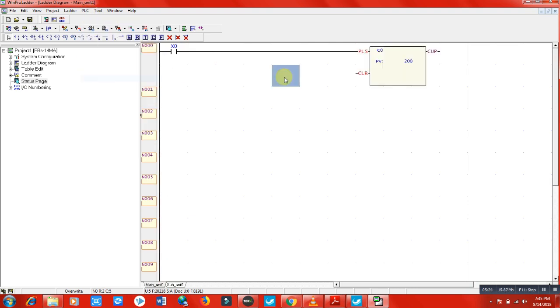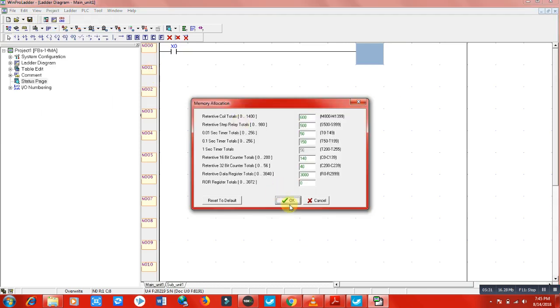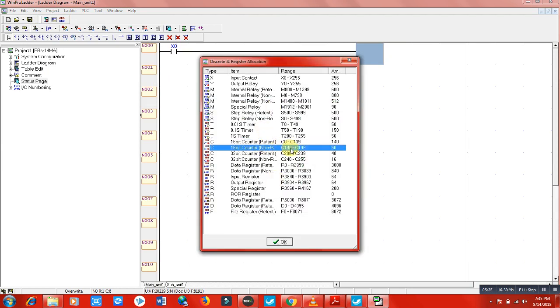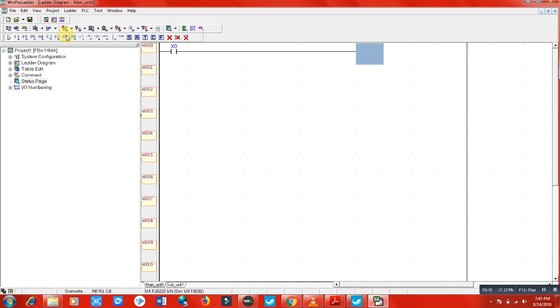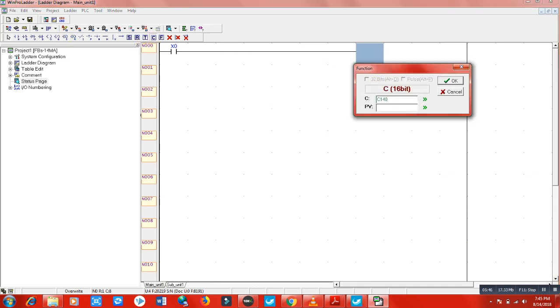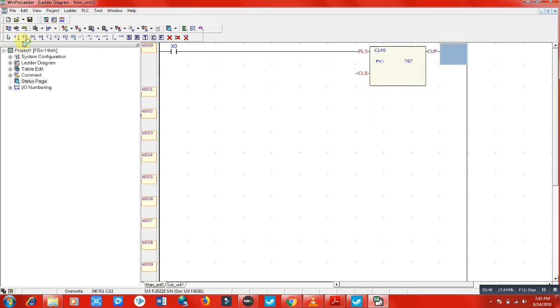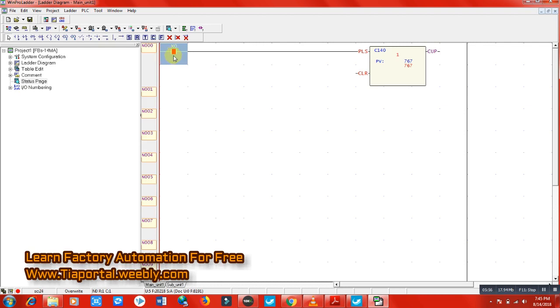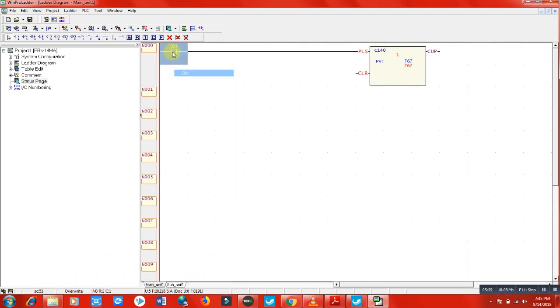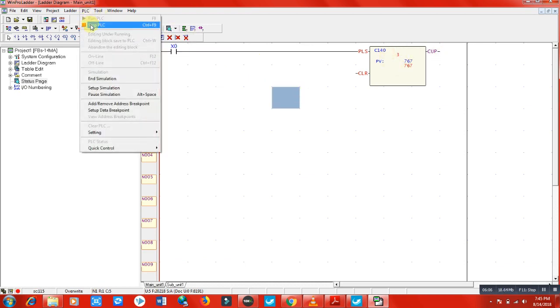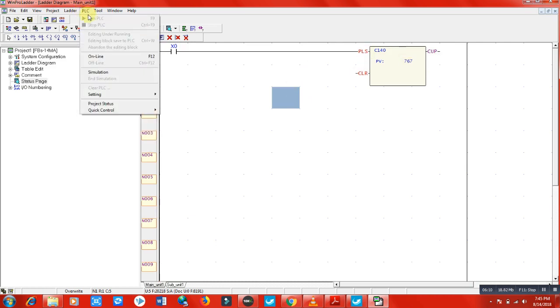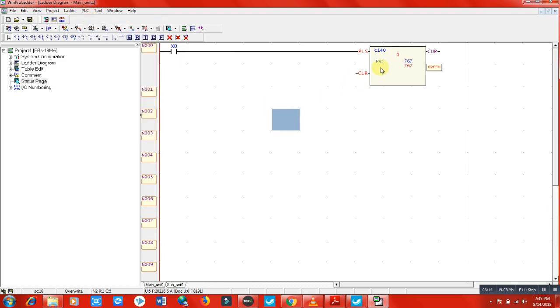Now let's use a non-retentive counter. Remove C0 and use C140 instead. We have a total of 60 non-retentive 16-bit counters starting at C140. Run the PLC and supply signal pulses — one, two, three. Now the value is three. I'll stop the PLC, end the simulation, restart, and run again — and it shows zero. The non-retentive counter did not remember its value.